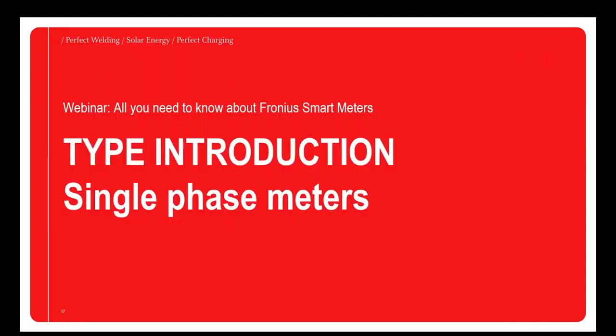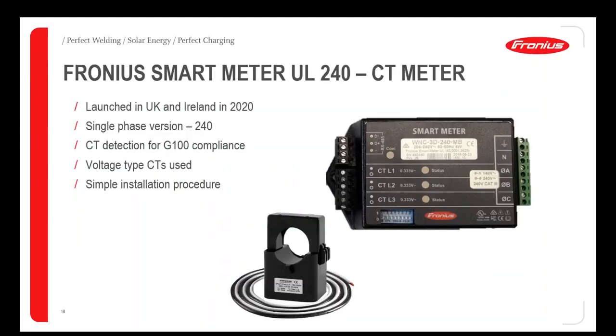So let's look at the smart meter itself. We've had a look at the functionality and the impact it has on the PV system. Let's have a look at the individual devices. Some of you who have been installing smart meters already may be familiar with the UL240 meter. Up until now, this has been the key meter for the single phase market. This is a CT meter, so it has a current transformer, which clamps around the incoming mains cable, measures the current, and then tells us which direction energy is flowing and the amount of energy being used on site. So it's a simple meter to install, but it does have to take its own enclosure.